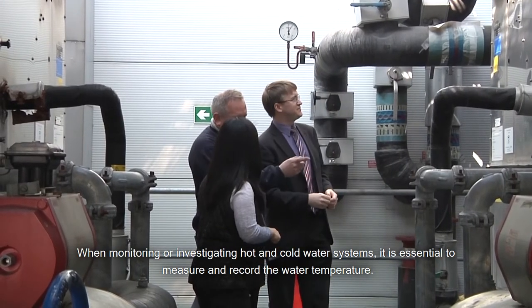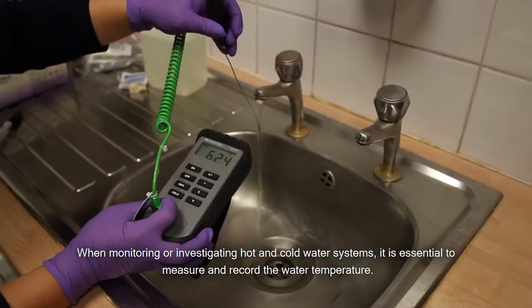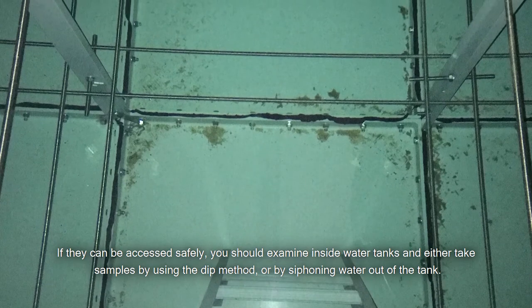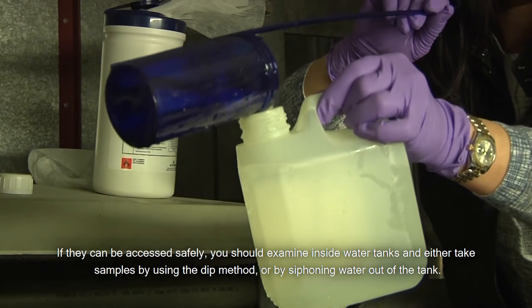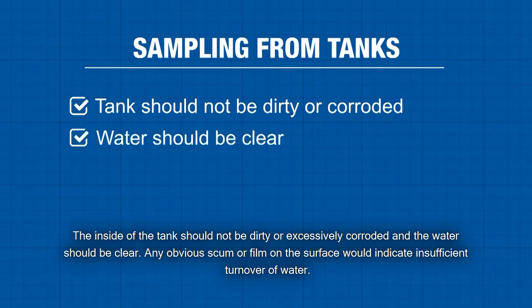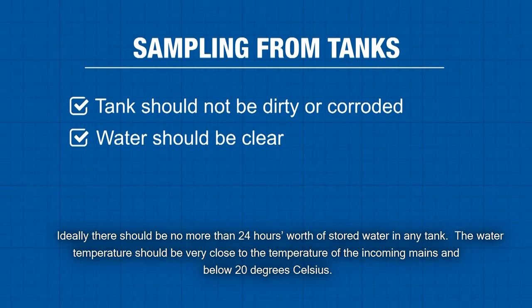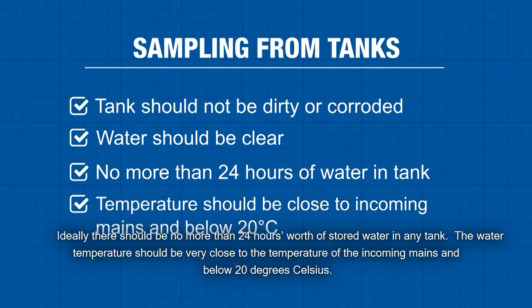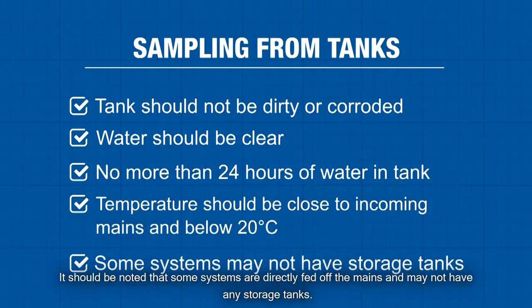When monitoring or investigating hot and cold water systems, it is essential to measure and record the water temperature. If they can be accessed safely, you should examine inside water tanks and either take samples by using the dip method or by siphoning water out of the tank. The inside of the tank should not be dirty or excessively corroded and the water should be clear. Any obvious scum or film on the surface would indicate insufficient turnover of water. Ideally, there should be no more than 24 hours worth of stored water in any tank. The water temperature should be very close to the temperature of the incoming mains and below 20 degrees Celsius.